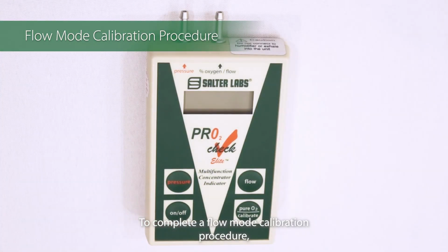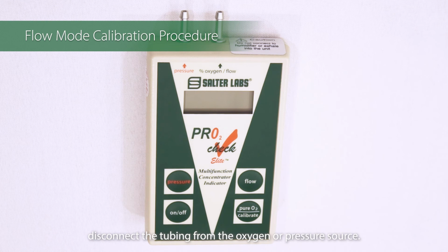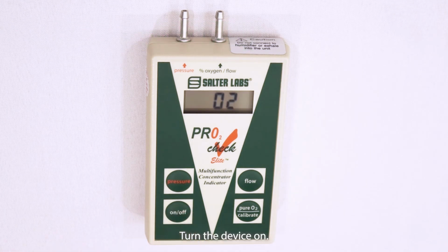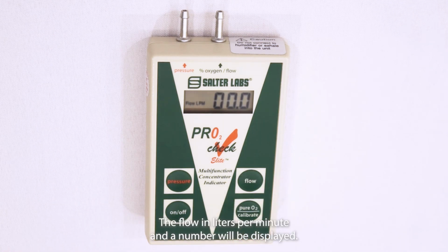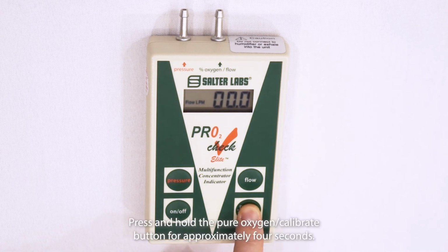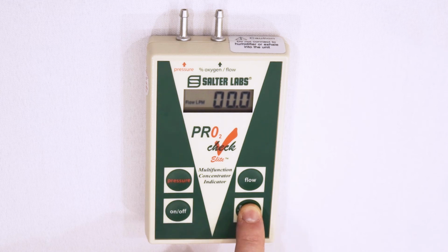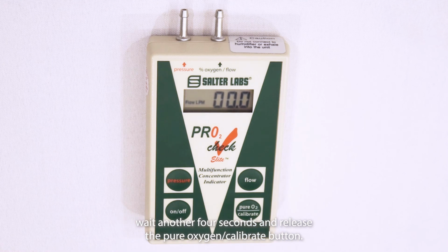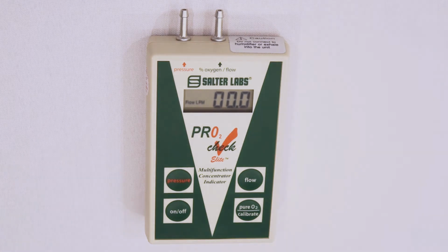To complete a flow mode calibration procedure, disconnect the tubing from the oxygen or pressure source. Turn the device on. Press the flow mode button. The flow in liters per minute and a number will be displayed. Press and hold the Pure Oxygen Calibrate button for approximately 4 seconds. The display will alternately flash 0.0 and Cal. Continue to hold down the Pure Oxygen Calibrate button. Wait another 4 seconds and release the Pure Oxygen Calibrate button. The flow mode is now calibrated.